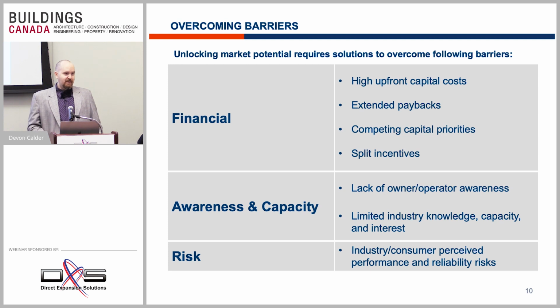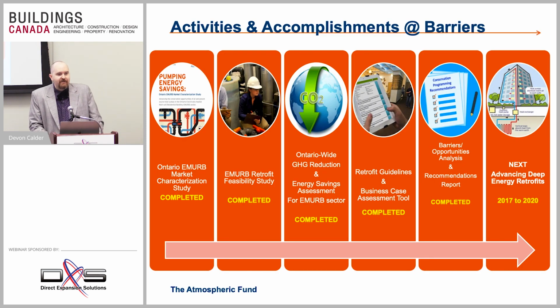But the reality is heat pumps have been around for decades. They're a proven technology. They're recognized globally as a key technology that can help reduce energy, both for heating and cooling. So those perceptions of risk, which are continuing to be a barrier for the market, are just that, perceptions of risk. Because what we find is that the new technologies of today can actually meet the heating and cooling demands that Ontario eMURBs require in a far more efficient manner than what's currently being seen. So how TAF is currently trying to address these barriers are through a number of activities.